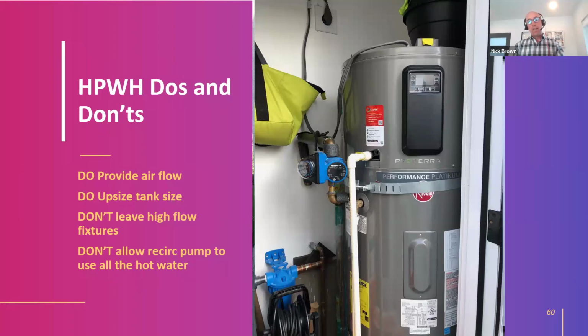Don't leave the 5-gallon-a-minute Speakman shower heads in houses with heat pump water heaters—they use a lot more hot water than necessary. Put in the code-compliant 1.8s. And don't allow recirculation pumps to work on a timer and suck up all that hot water before people get in the shower.